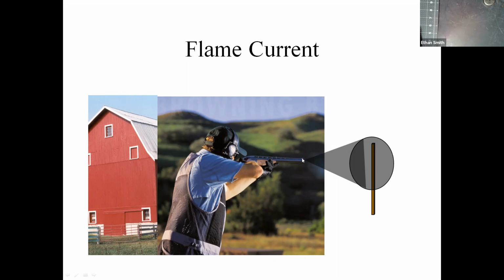So this is what's called DC flame rectification. And we end up being able to measure how much current we're drawing through that circuit. And so when we talk about flame current, we're actually talking about the DC current that's being rectified through our flame sensor. So this brings up a good point. When you guys are testing flame current, it might be a good idea not to hold on to it with your fingers, because we are sending up to 120 volts through these flame sensors. I've worked on commercial equipment that sends 230 volts out to a flame sensor before, and it'll light up your life a little bit.